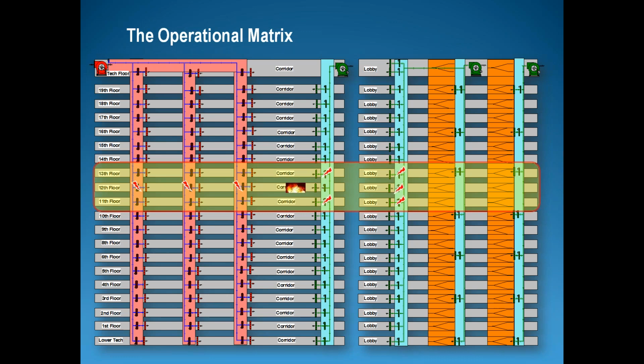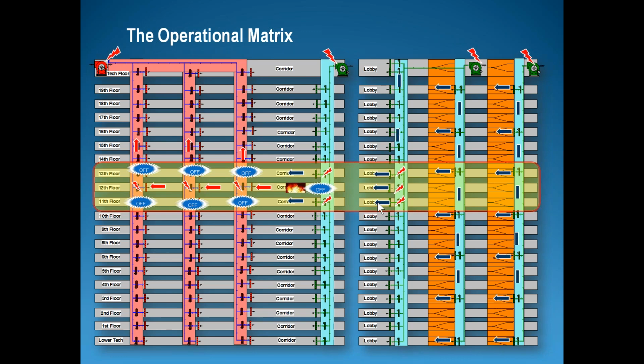Okay. This is energized, you can see these dampers are energized for smoke extraction. And these dampers on the upper and lower floors or stories will close. So these floors will be pressurized. We can say that we are making a sandwich. You are feeding air into the stairs, pure fresh air, and you make an extraction from the affected floor. So you can say that we made the sandwiching of the extraction.